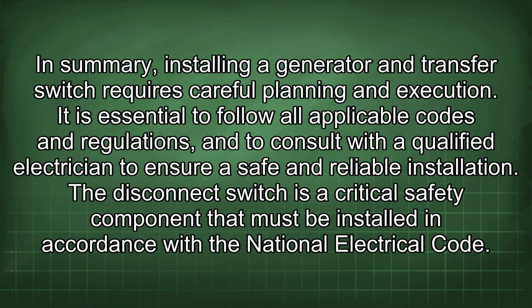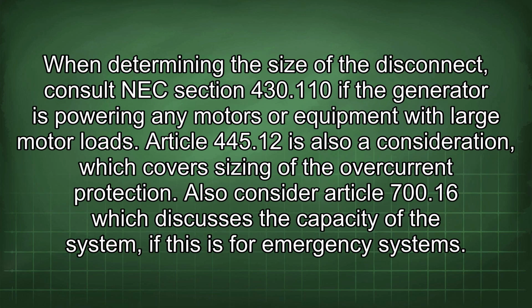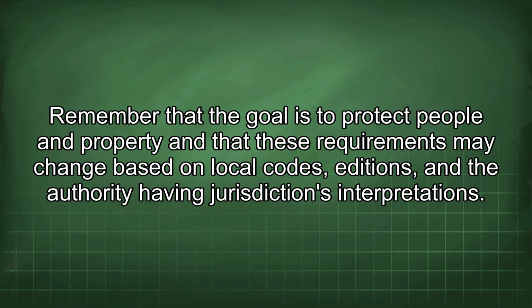safe and reliable installation. The disconnect switch is a critical safety component that must be installed in accordance with the National Electrical Code. When determining the size of the disconnect, consult NEC section 430.110 if the generator is powering any motors or equipment with large motor loads. Article 445.12 is also a consideration, which covers sizing of the overcurrent protection. Also consider Article 700.16, which discusses the capacity of the system, if this is for emergency systems. Remember that the goal is to protect people and property, and that these requirements may change based on local codes, editions, and the authority having jurisdiction's interpretations.